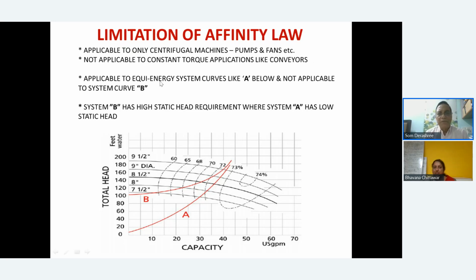It is applicable only to equi-energy system curves like A. Now you see in A, as it goes down, the efficiency stays at 72 to 73%. This curve, up to here, is all 72 to 73%. There's not much change in efficiency. But if you are talking of B, you see the efficiency is falling from 72% to only 60% when you come here. In this case, you are bound to create a problem of static head, because here the head requirement is much higher compared to A. So here putting a VFD might land you in a problem. So you have to be very careful where you use a VFD and apply the affinity laws to save energy.